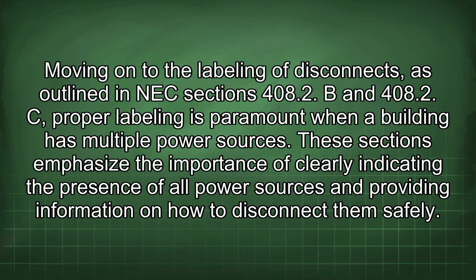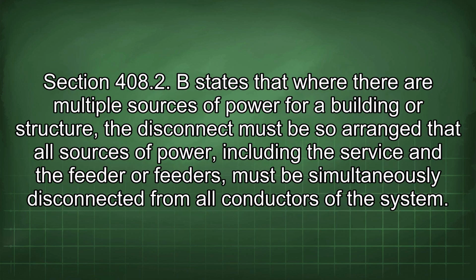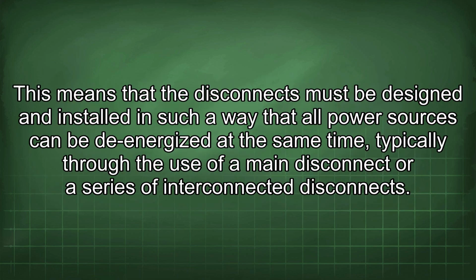disconnect them safely. Section 408.2 B states that where there are multiple sources of power for a building or structure, the disconnect must be so arranged that all sources of power, including the service and the feeder or feeders, must be simultaneously disconnected from all conductors of the system. This means that the disconnects must be designed and installed in such a way that all power sources can be de-energized at the same time, typically through the use of a main disconnect or a series of interconnected disconnects.